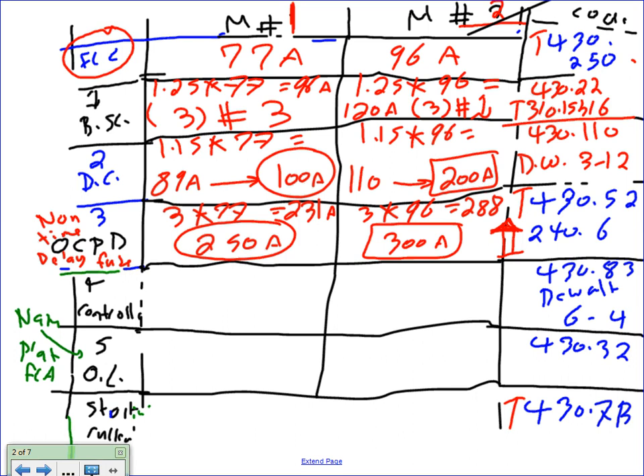Controllers are a piece of cake. They are sized based on the voltage. So 60 horsepower at 480 will get you a NEMA 4. And where do I get NEMA 4? This is 430.83, Table 6-4. Is it still 6-4? I don't think they changed it this year. Make sure you know how to use Table 6-4. It's based on the voltage and the horsepower. It'll give you the NEMA size, the contactor.